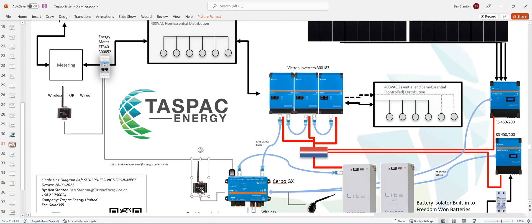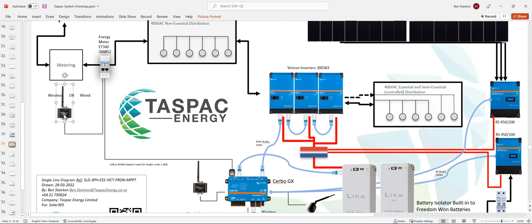If it's in a different building or further than 10 meters away, then you use the wireless, and that will go however far wireless goes. So it depends on the environment, depends on the cladding of the building. If it's a metal building, you probably don't want to rely on it for more than about 30 meters. But that uses Zigbee, high power radios, point-to-point wireless. So those are also supplied.